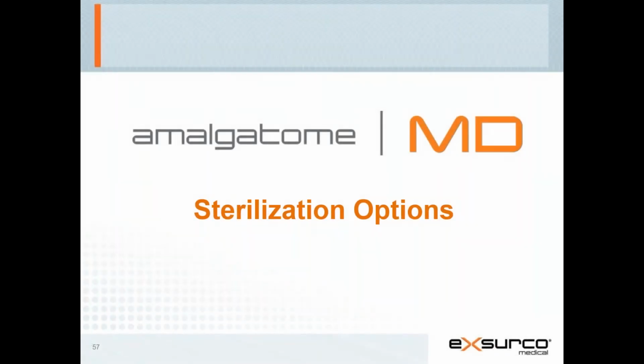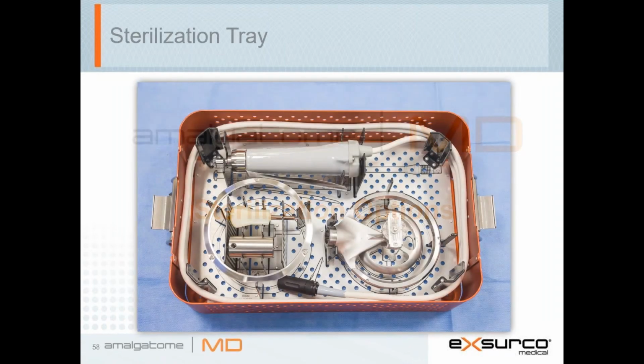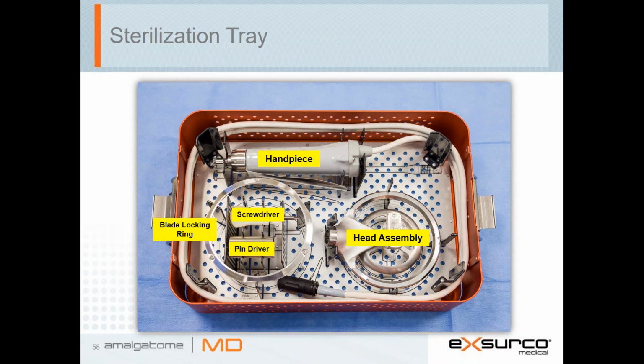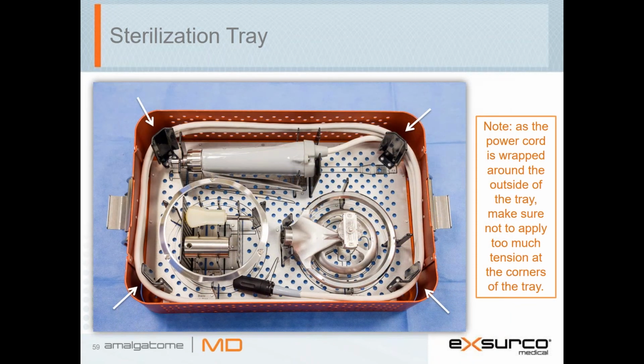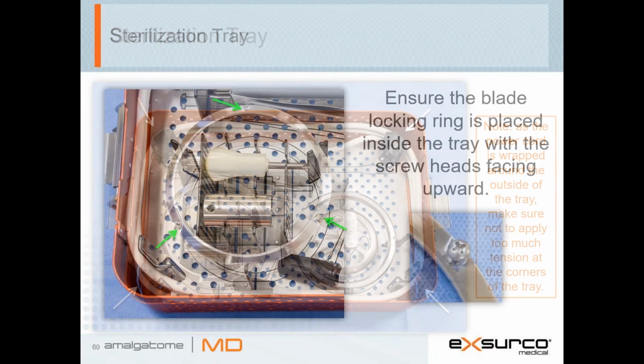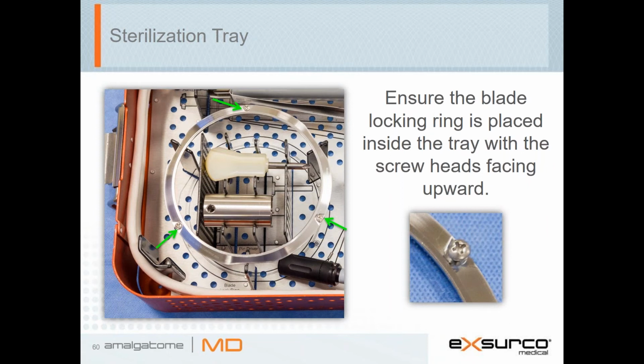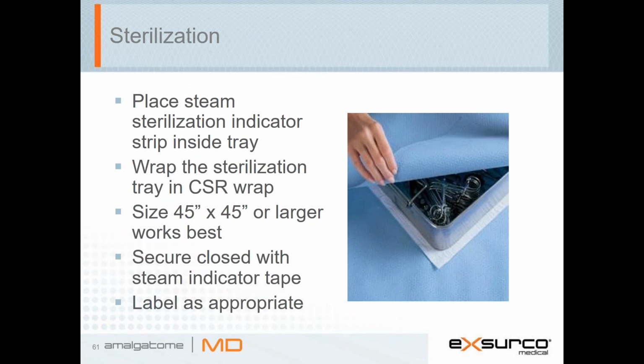Sterilization options. After disinfecting, place the handpiece, head assembly, blade locking ring, screwdriver, pin driver in the Amalgatome MD sterilization tray. Ensure the power cord is wrapped around the brackets located on the outside of the tray. Ensure the blade locking ring is placed inside the tray with the screw heads facing upward. Place steam sterilization indicator strip inside the tray.